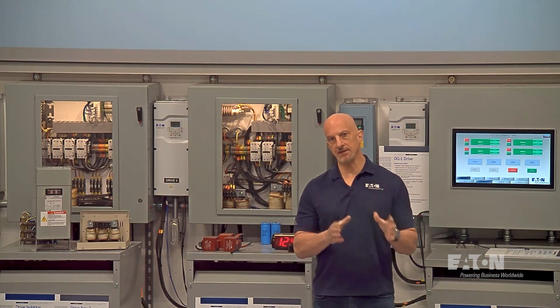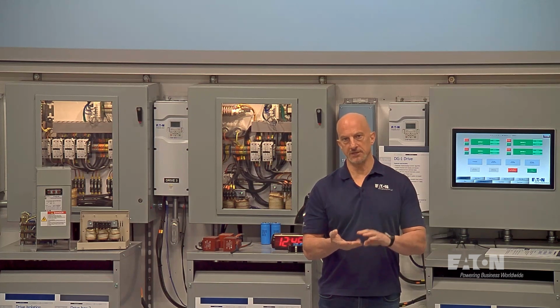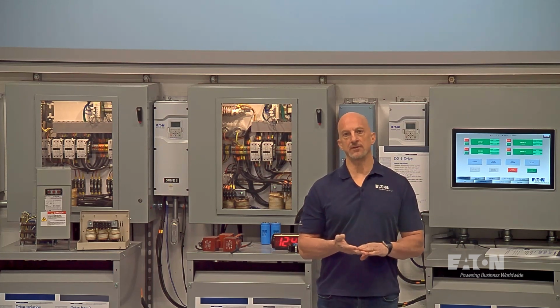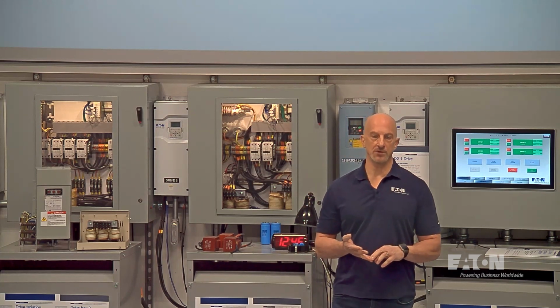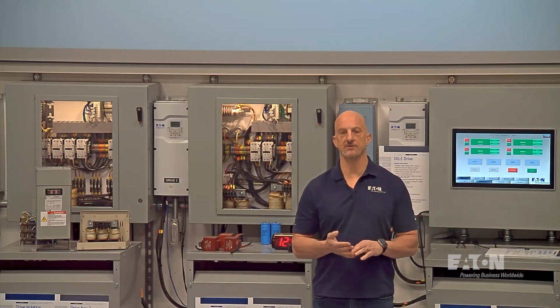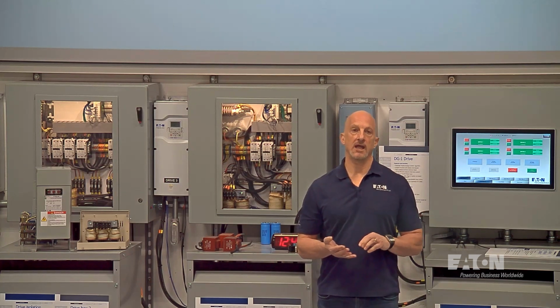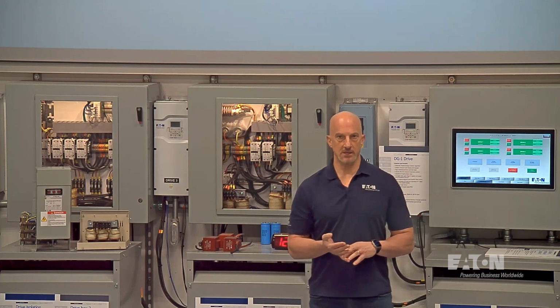So if you look at the differences in the three standards, 1992, 2014, 2022, the main difference in 2022 is the DERs. The main difference in the 2014 is the 5% went to 8% for low voltage distortion limits on voltage, and statistical information was put into the 2014.